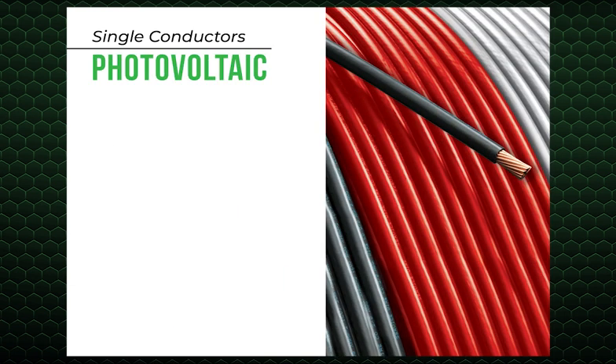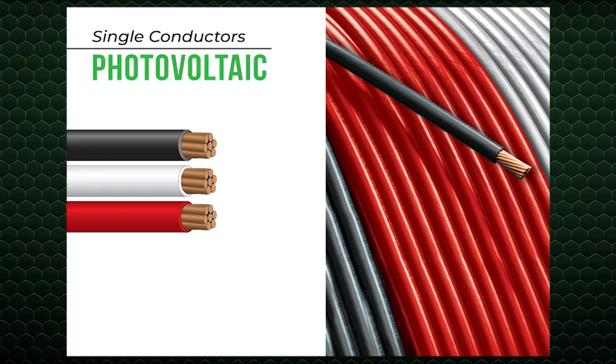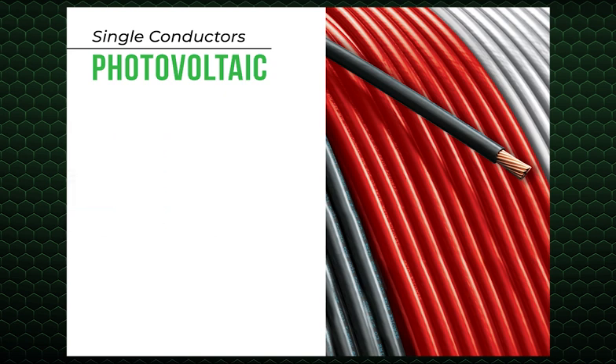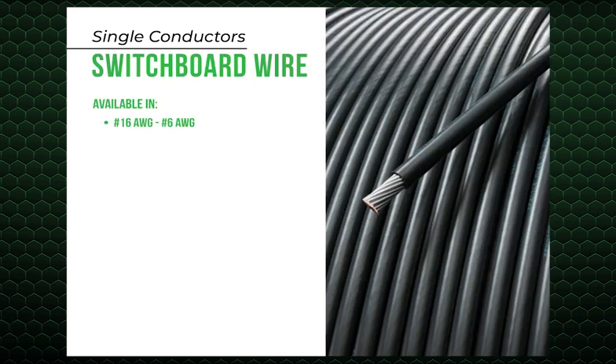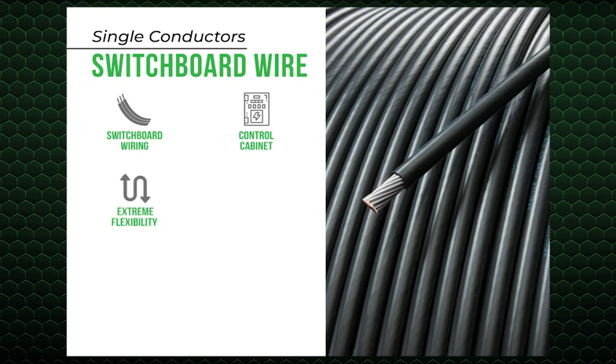Service Wire's photovoltaic wire is available as USE-2 or RHW-2 in 14 gauge through 750 kcmil, 600 volt or 1 kV/2 kV in black, white, or red XLPE insulation. PV wire is used as interconnection of solar panels and grid connecting feeders. Switchboard wire is available in 16 gauge through 6 gauge, 600 volt/1 kV tinned copper. SIS is used in switchboard wiring, control cabinet, other instrumentation applications where extreme flexibility is required, and 105 degrees Celsius dry systems.